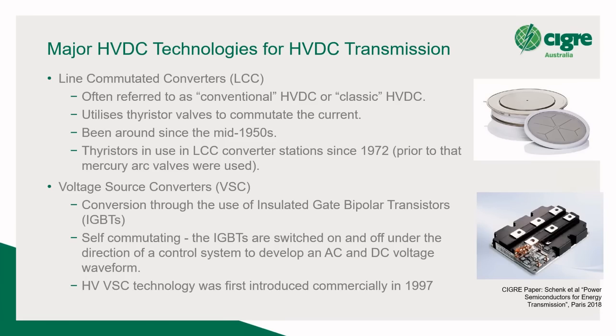So in terms of technologies, there are two major technologies. There are variants of these, of course, but major technologies for HVDC transmission: line commutated converters, LCC. I'll refer to them as LCC in this webinar. Often referred to now as conventional or classic HVDC. It's, of course, until VSC came along, it was only referred to as HVDC. They utilize thyristor valves to commutate the current instead of IGBTs, which are used by voltage source converters. The technology has been around since the mid-1950s. The early thyristors have been used since the early 1970s. Prior to that, they used mercury arc valves, which I understand all of them now are decommissioned and in some way replaced with the thyristor.